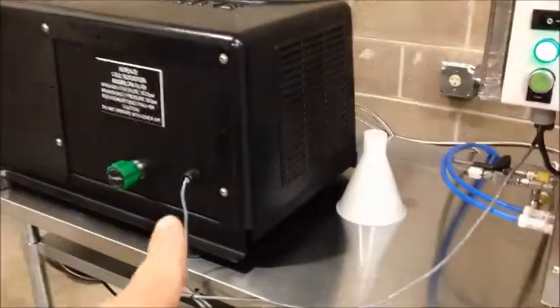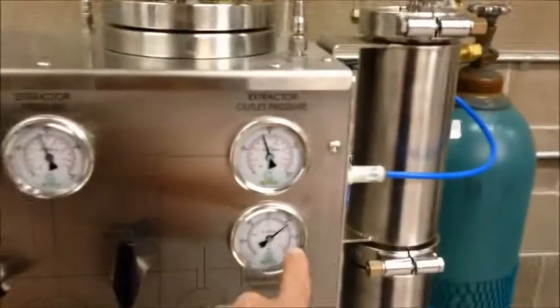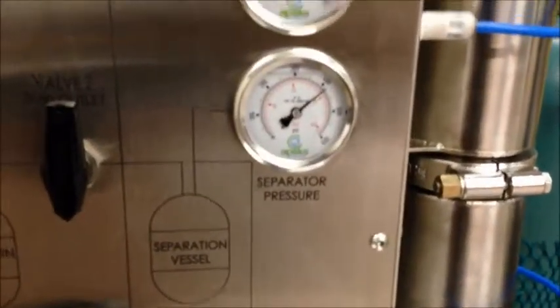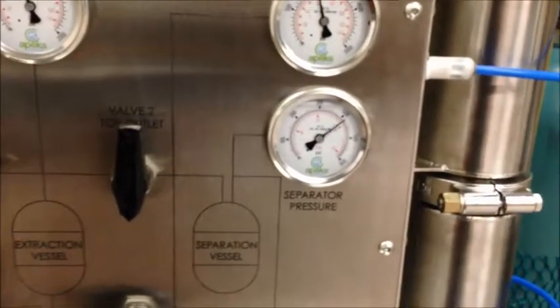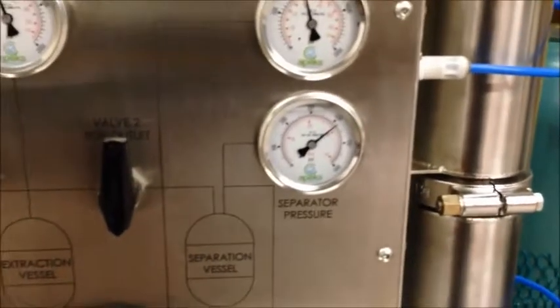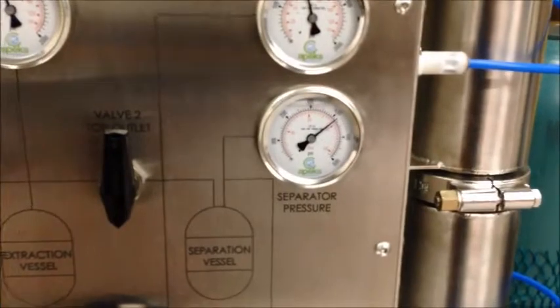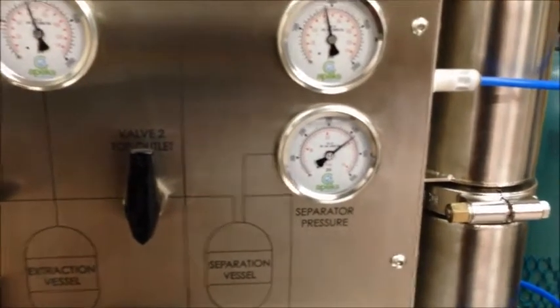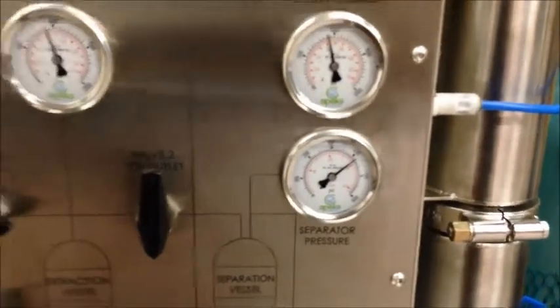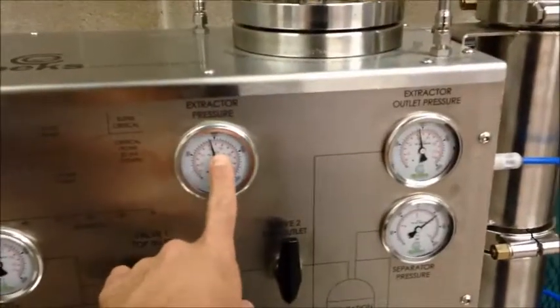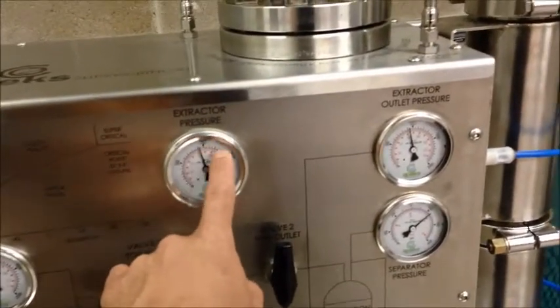And every 5 or 10 minutes, check it, readjust the green valve. And the goal is to keep this right around 420. So as you can see, I've already got mine set. Once you get it set, you don't need to mess with that green valve every time. Maybe every other time or so, you may need to check it, but for the most part, it should stay pretty steady. So now what's happening? I'm just watching. Our extractor pressure will eventually get between 1,000 and 1,200 psi, and this should be around 420.